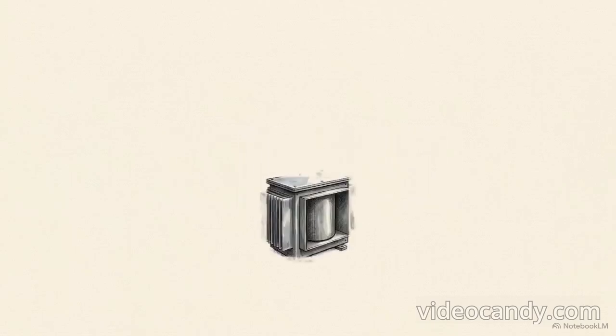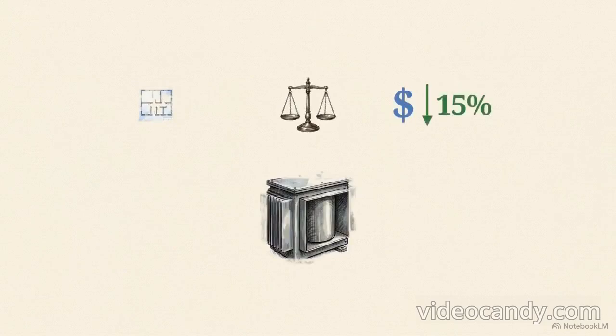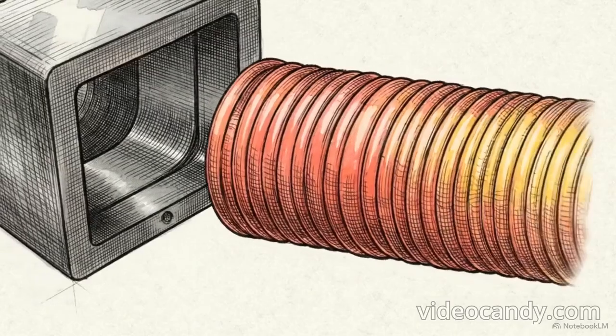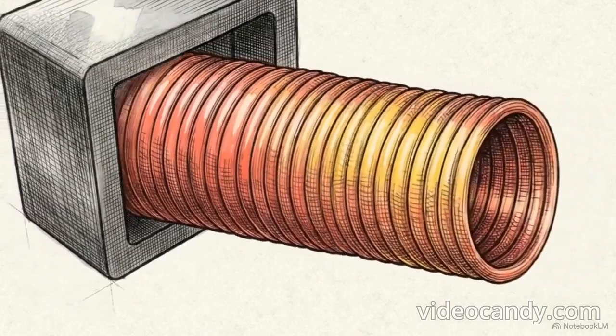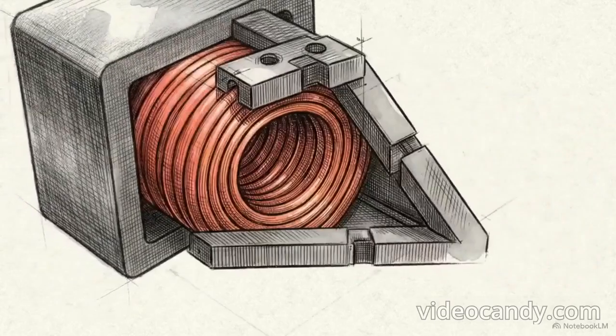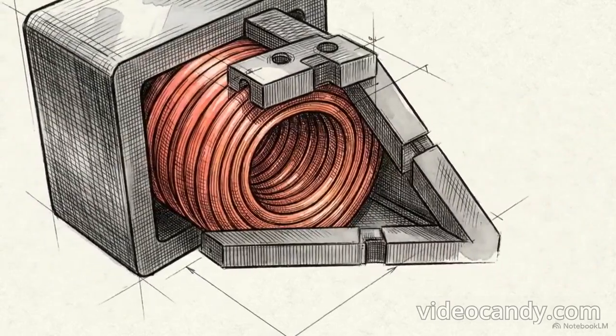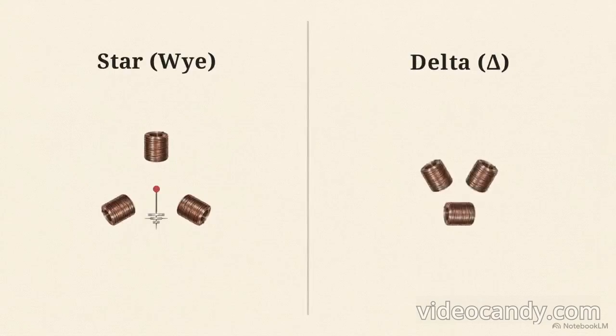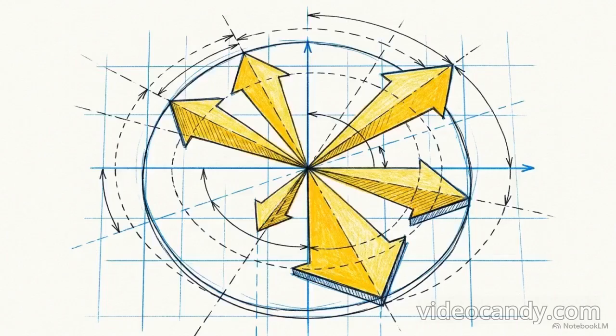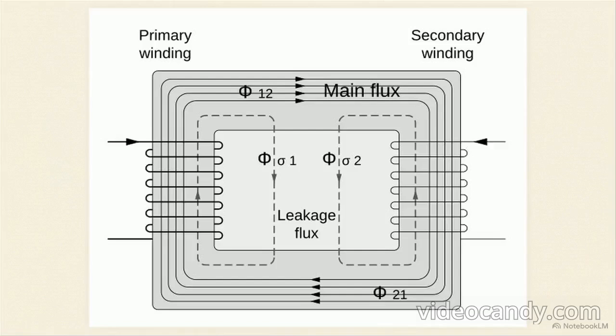Consolidating 3 units into one reduces the required floor space, cuts the total weight, and lowers manufacturing costs by about 15%. But packing 3 phases into a single casing requires precise alignment. The internal mechanics rely entirely on exact phase geometry. Inside the iron, engineers must choose between 2 foundational wiring topologies, the star, also known as Y, and the delta connection. These specific internal configurations dictate how phase vectors and voltages are manipulated, setting the mathematical limits for the entire system.